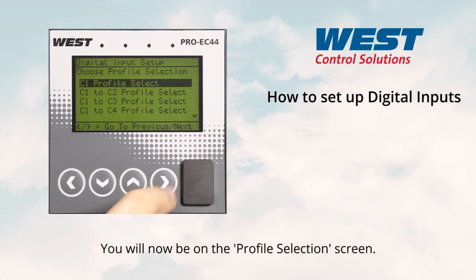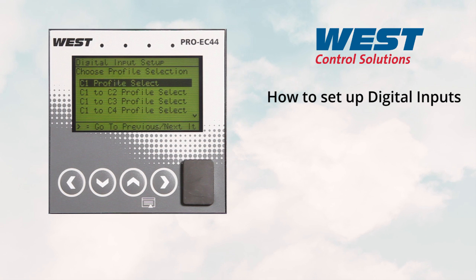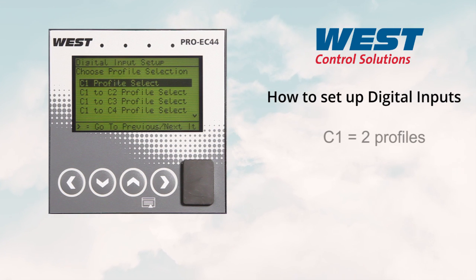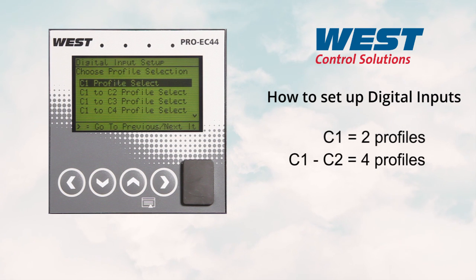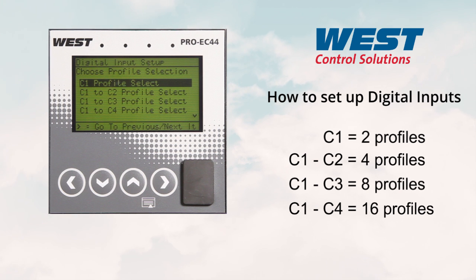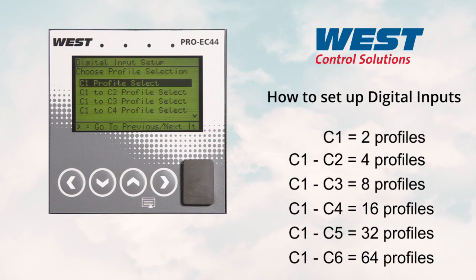You will now be in the profile selection screen. Please note that this screen will not show if you selected none on the previous profile selection screen. Choose the profile selection for how many profiles you want to control through digital inputs: C1 equals 2 profiles, C1 to C2 equals 4 profiles, C1 to C3 equals 8 profiles, C1 to C4 equals 16 profiles, C1 to C5 equals 32 profiles, C1 to C6 equals 64 profiles.